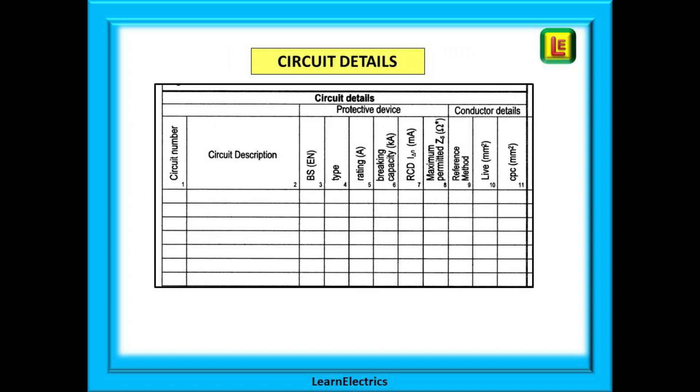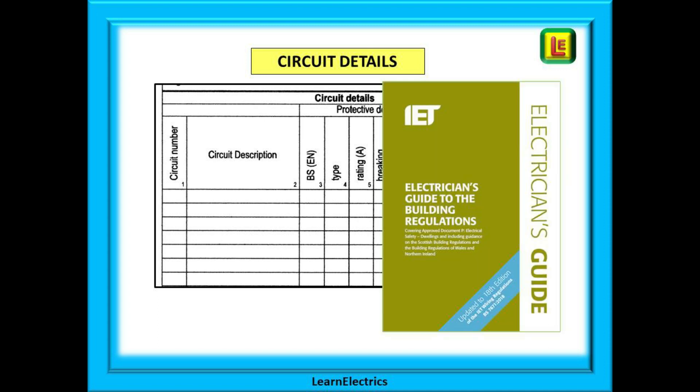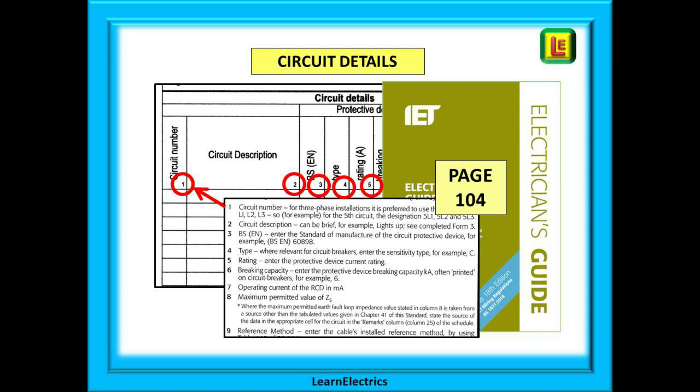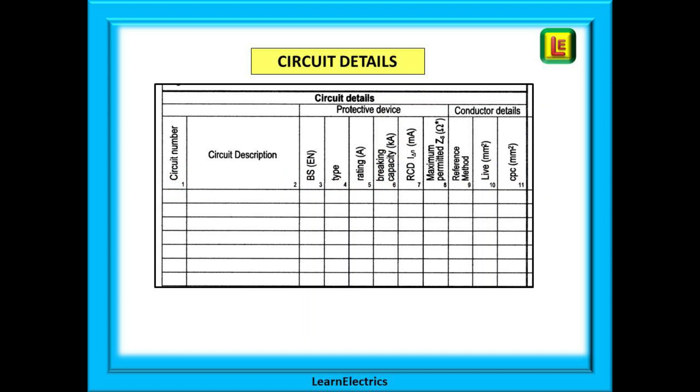And now to the two big boxes. The circuit details section can be completed by visual inspection and knowledge of what is in the consumer unit without the need for any testing. Personally, I always complete all of this section before moving on to the testing section. This is where the electricians guide to the building regulations comes in very useful. If you have a copy of the electricians guide, turn to page 104. There you will find a list. Look at the schedule of test results and each column in this section has a small number at the top. The information in the list on page 104 relates directly to each of these column numbers and I have circled them in red on this slide. So, let us complete this circuit details section as I would complete it.